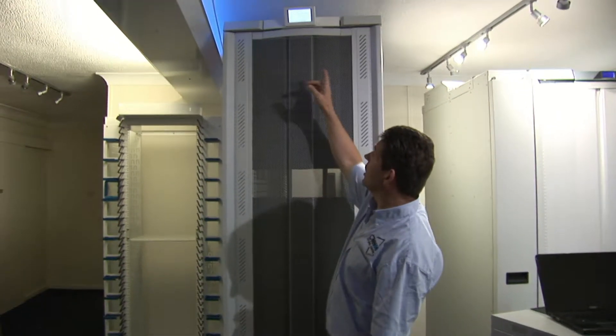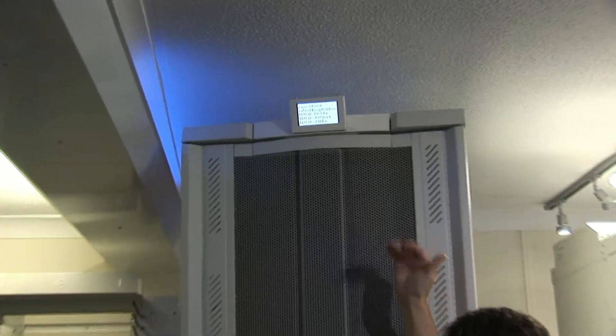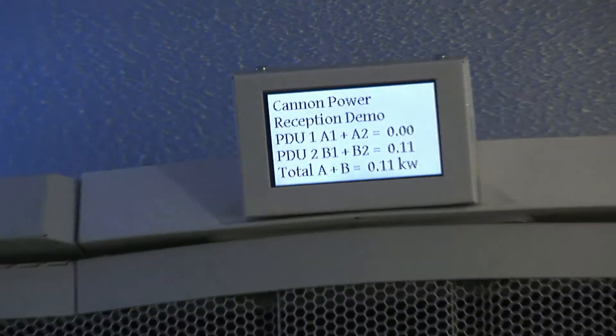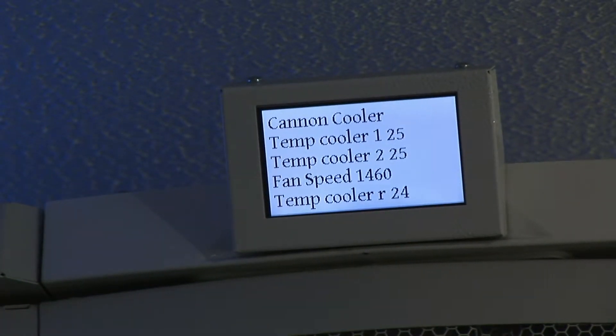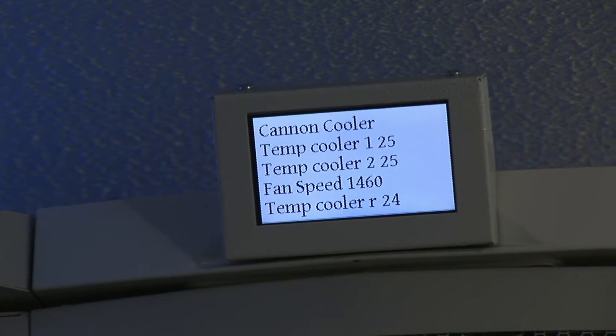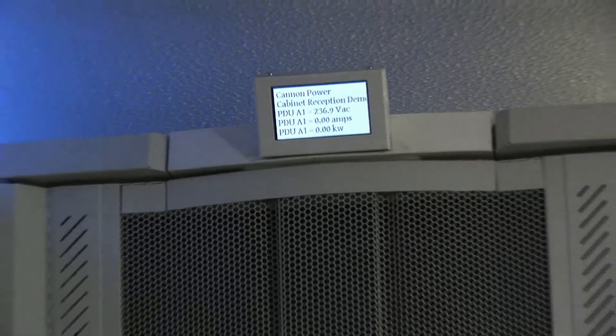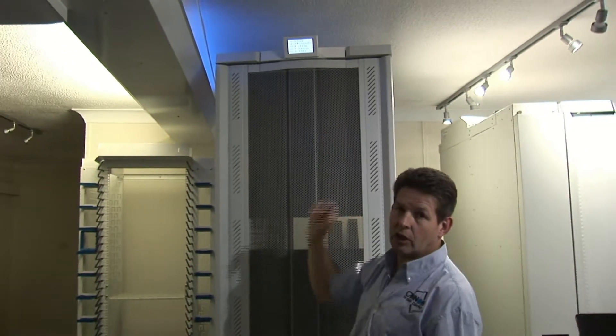On this neighbouring cabinet we can see the large four and a half inch colour display. It displays the status of the power and cooling, and can also show a colour logo with the background. The alarms can also change colour — for instance, if a fan fails it will show in red on that display. These displays are available to fit to both the front and rear of the cabinet, and can also be at the end of aisle.